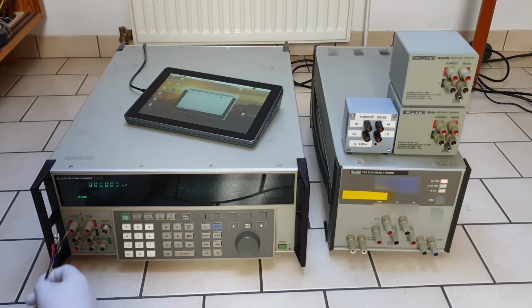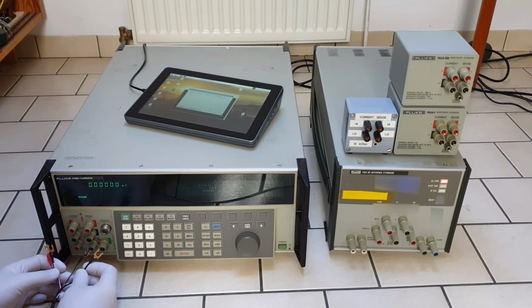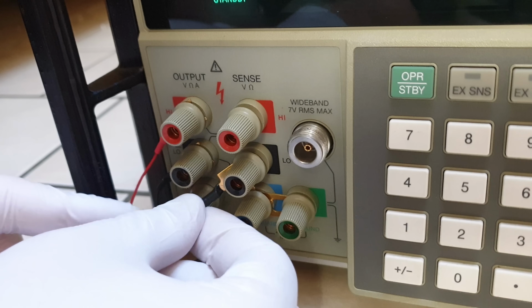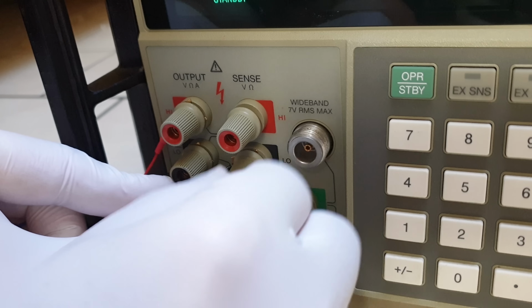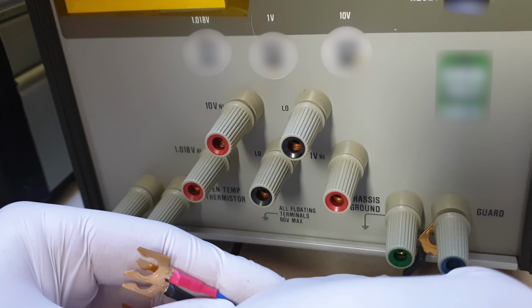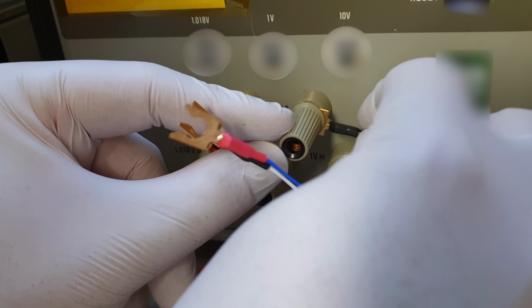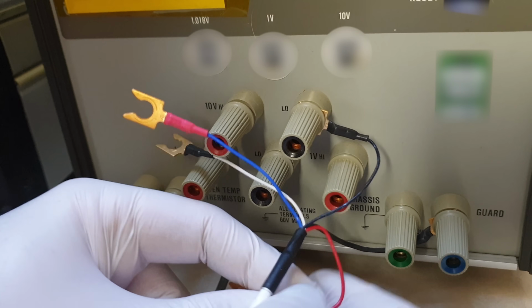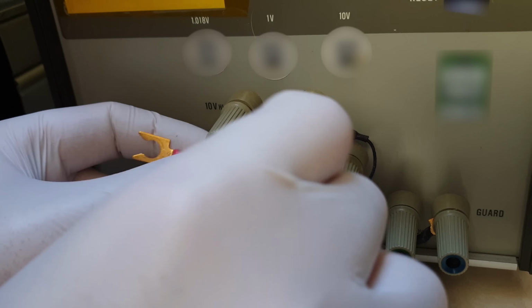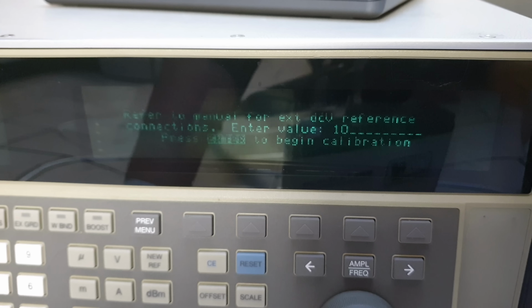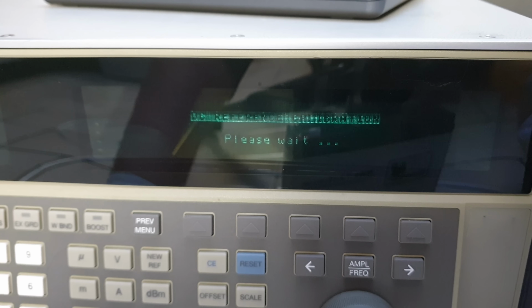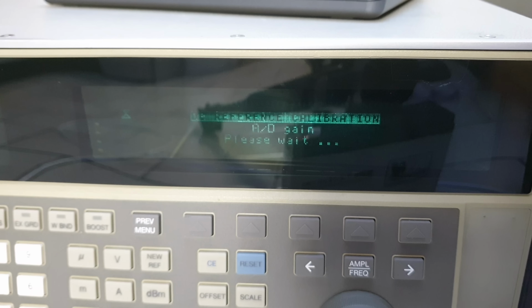The Fluke 732A preventive maintenance actually took place last year, and I've monitored it intermittently since then, both using voltmeters and calibration reports generated by Fluke 5700. Not even a hint of another jump appeared since then. If anything, the two Flukes seem to agree with each other too closely, as if they are conspiring to save each other's skin. This, by the way, is why I was questioning the external trim capabilities of both the standards we've seen today. All devices that matter give you the opportunity to enter the precise value of the reference that's used.